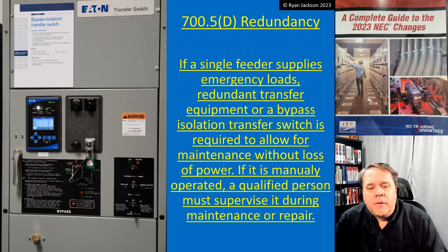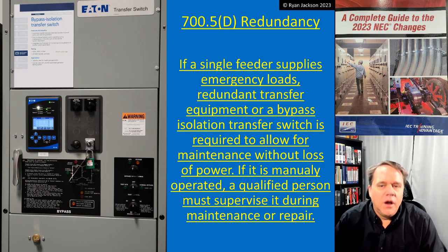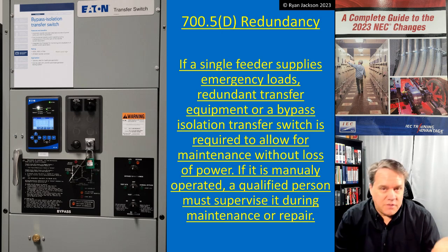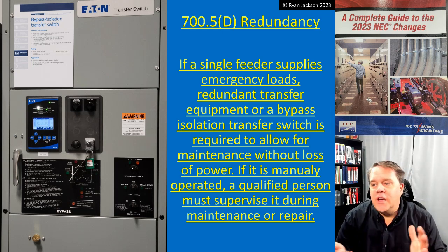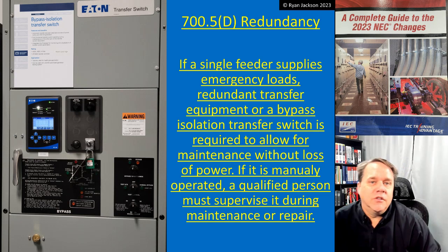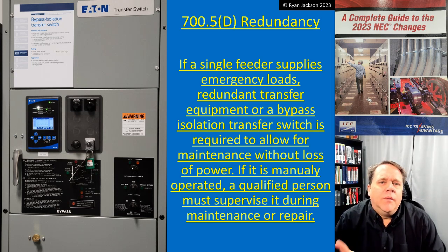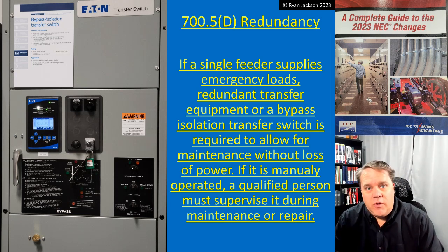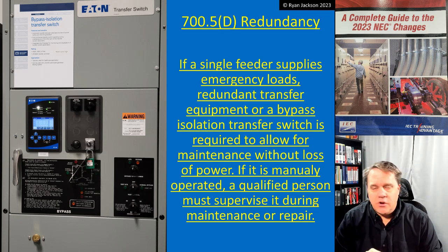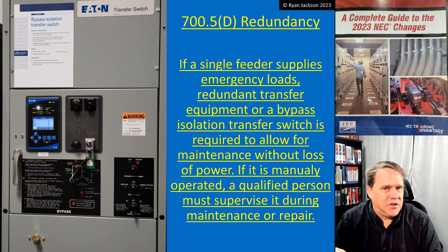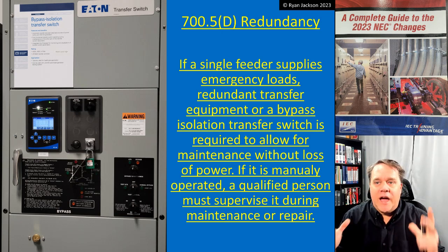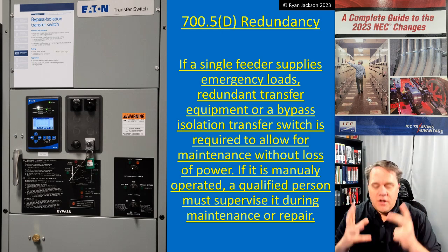If it's manually operated, a qualified person needs to supervise it during maintenance or repair. We're recognizing that things need to be maintained. Now let's be clear — we're talking emergency power, not optional standby. The generator at your house is not an emergency system. When we're talking about emergency systems, we're talking about big commercial buildings, high-rises, hospitals — legally required emergency systems.